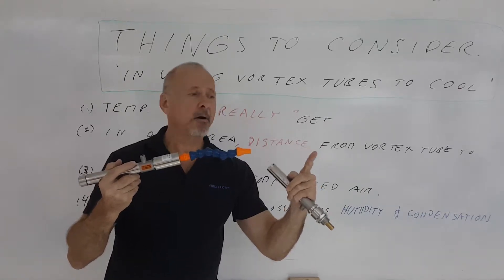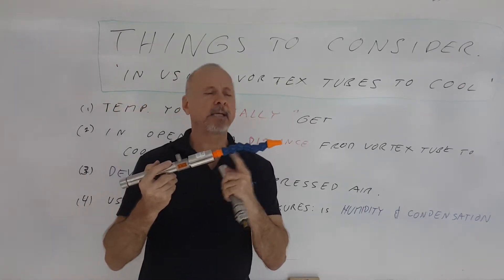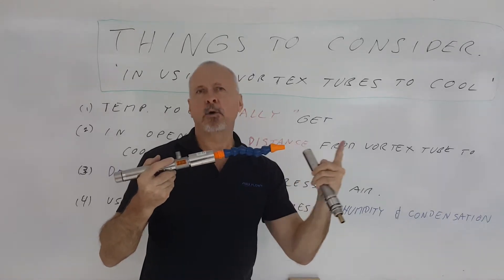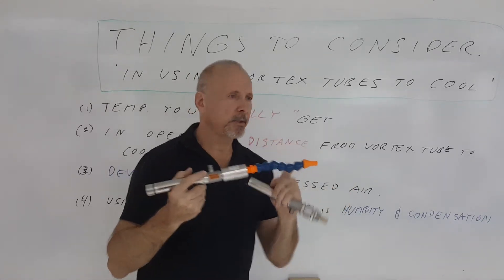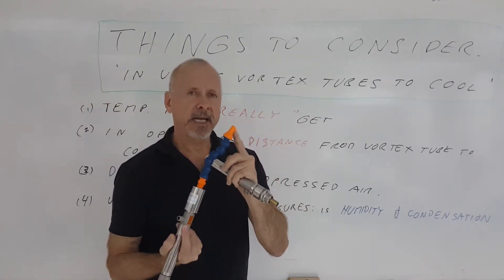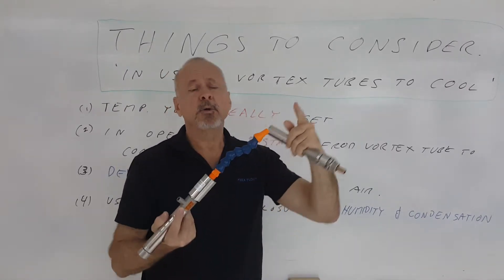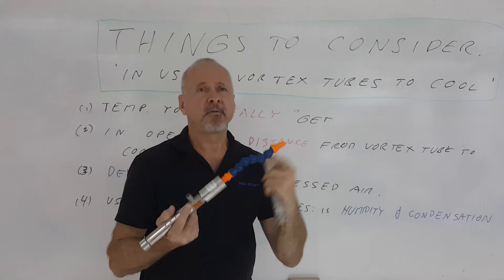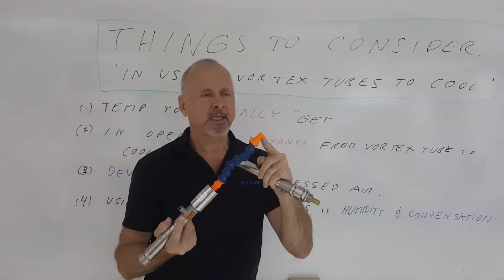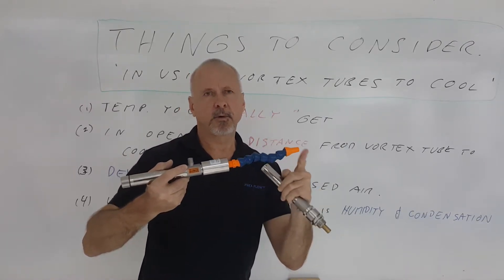So you have to consider how far the distance is. To really keep the temperature as cold as possible, you want to minimize that distance from the vortex tube to about six inches — any more than that and it's going to start warming up more. Not only the distance, but also the inside diameter of the delivery tube matters. If that inside diameter is too small, you're going to create back pressure and that will affect the performance of the vortex tube. So you want to minimize back pressure by maximizing the internal diameter and minimizing the distance from the vortex tube to the point of use.